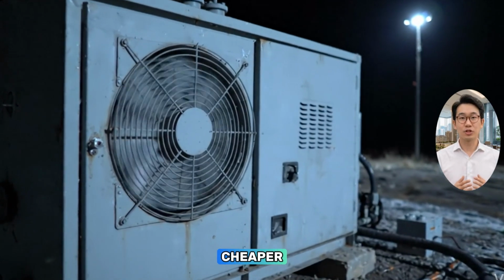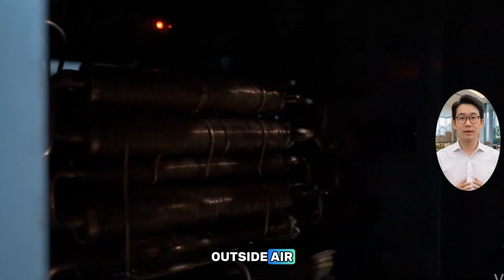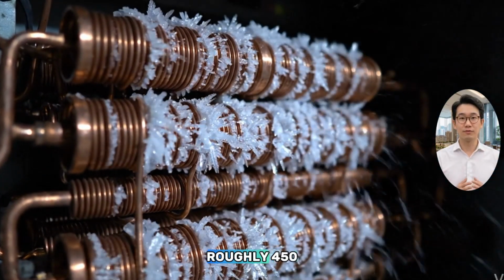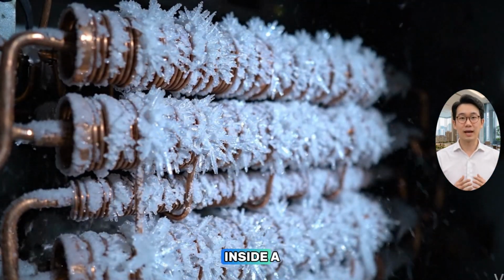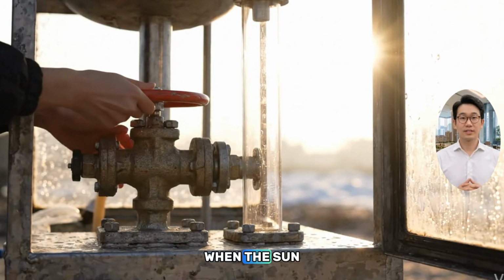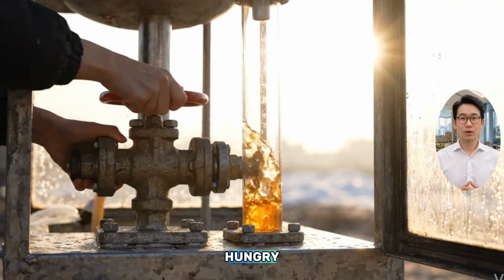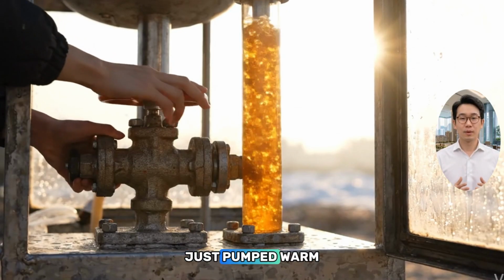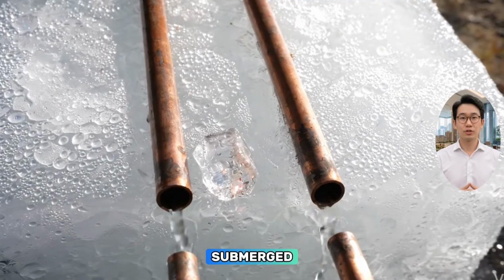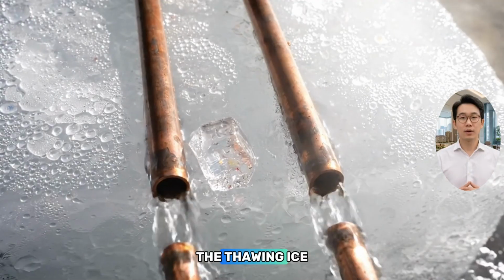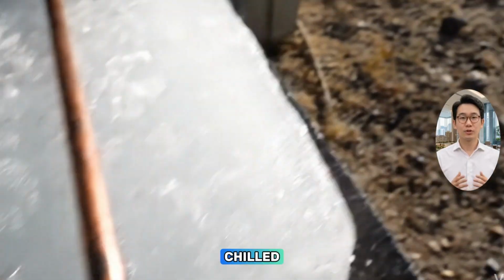Overnight, taking advantage of cheaper grid power and cooler outside air, the machine's compressor would freeze roughly 450 pounds of water inside a built-in reservoir. When the sun came up, rather than firing up that power-hungry compressor again, the system just pumped warm refrigerant through tubing submerged in that solid block. The thawing ice chilled the fluid, which chilled the house.